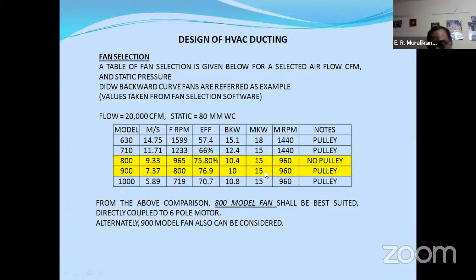But what happens is many people ignore this motor RPM. They blindly go for a four-pole motor or a two-pole motor, which is commonly, easily available off the shelf. In this case, if I put 1440 RPM for both the applications, my pulley loss will be higher because from 1440 I have to change to 960, with belt loss, everything. But if I directly go for a six-pole motor, which will give 960 RPM, it is okay for me because 960, 965 is very close, no issues.